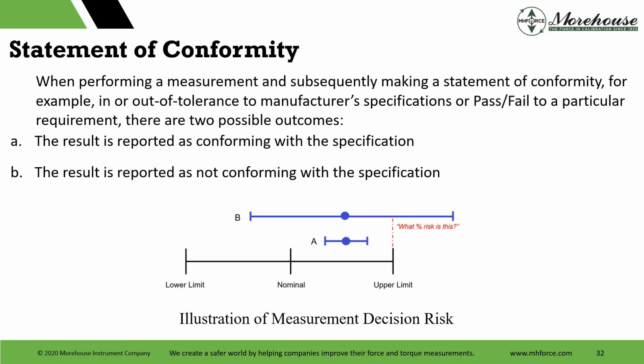So, statement of conformity. When performing a measurement and subsequently making a statement of conformity, for example, in or out of tolerance to a manufacturer specification, pass or fail to a particular requirement, there are two possible outcomes. This is from the ILAC G8. The result is reported as conforming with the specification. Yay, there's much rejoicing when that happens. That's the best thing you want to see, something that conforms. Or the result is reported as non-conforming.